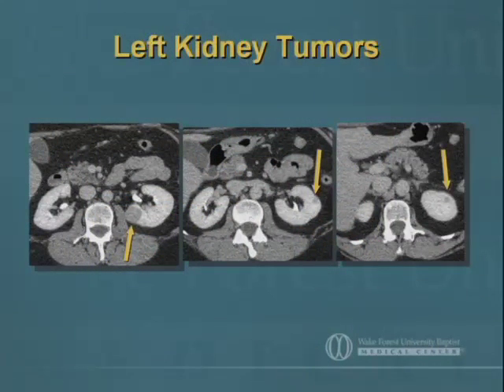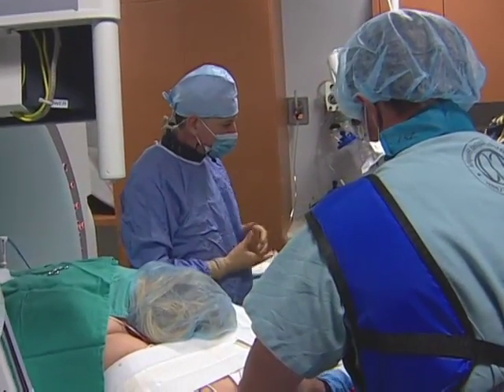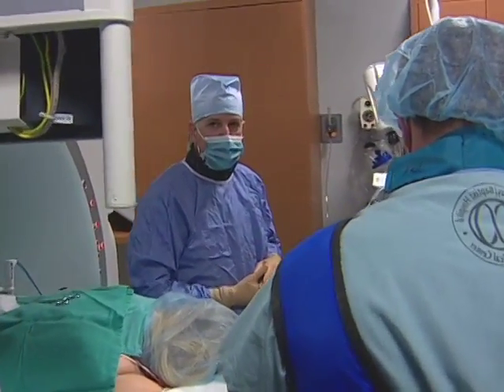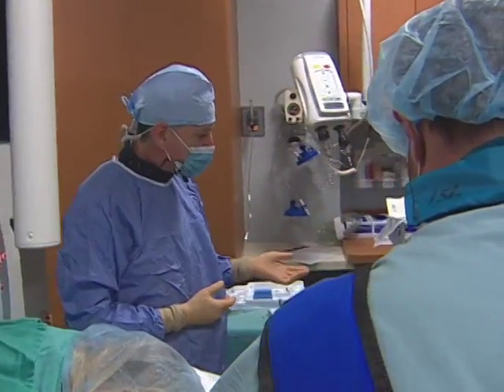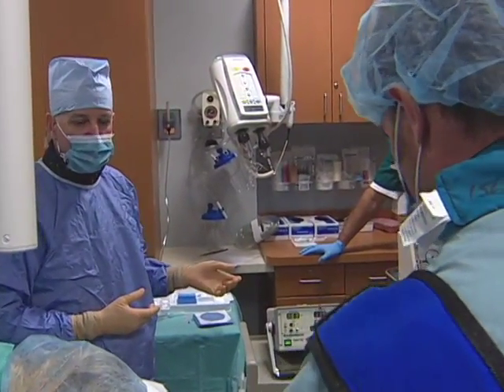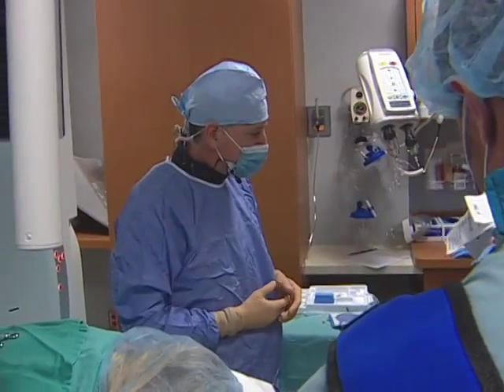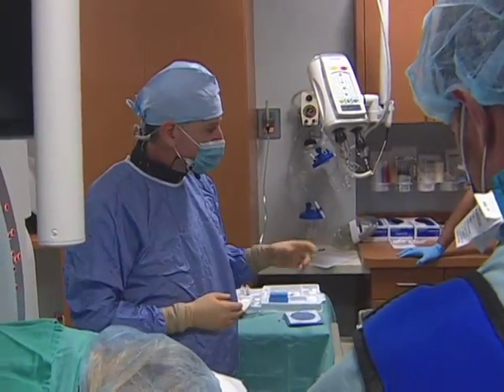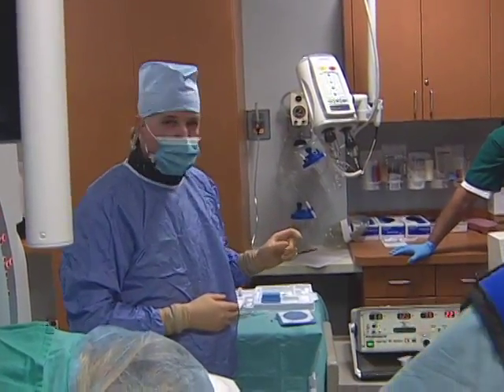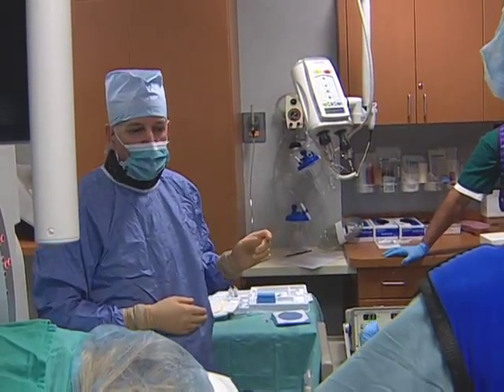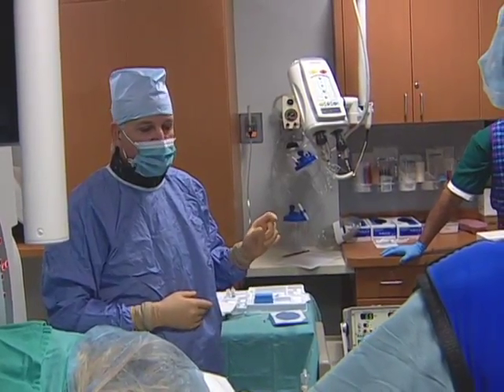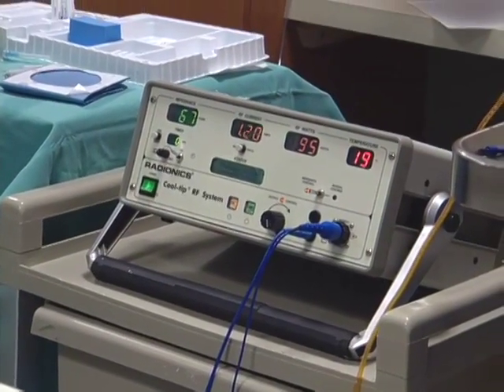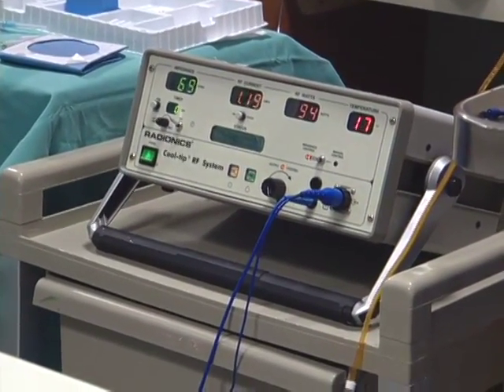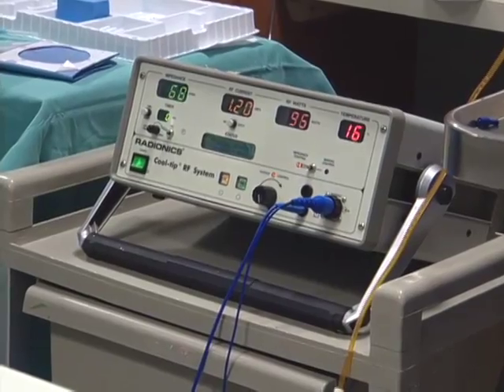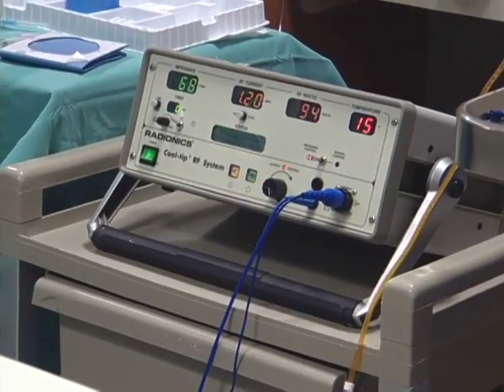So now we're using a water-cooled ablation device. We turn this on impedance control, which is sort of the standard setting that does autopilot. This device, the water cooling and the pulsation setup of this allow you to get a larger ablation zone. The water cooling cools the temperature of the area immediately around the exposed portion of this antenna. The final 3 centimeter tip of this is exposed. It emits the radio frequency energy, allowing for a generation of a large volume of heat.